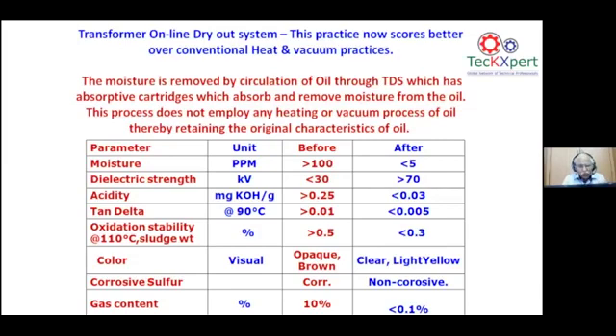Also the corrosive sulfur has become totally non-corrosive. Visibly, the opaque brown color of the oil has become clear and light yellowish in color. Gas content also comes down. So this is going to take over, especially in the transformer dry out system. Instead of the offline dry out system, the online dry out system with these absorptive type cartridges will continuously remove the moisture. It will be kept on along with the transformer as an auxiliary, and it will remove the moisture from the transformer.